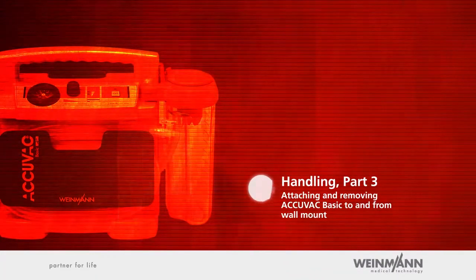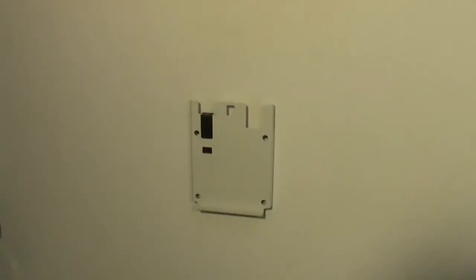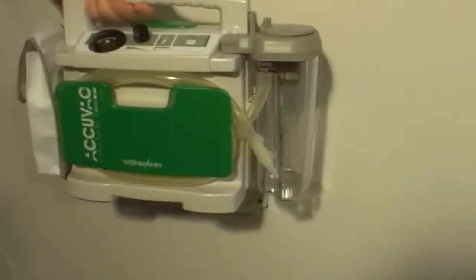Handling, part three: attaching and removing ACCUVAC Basic to and from wall mount. After use of ACCUVAC Basic outside the ambulance, the suction pump should be put back into its wall mount, where it can again be charged.